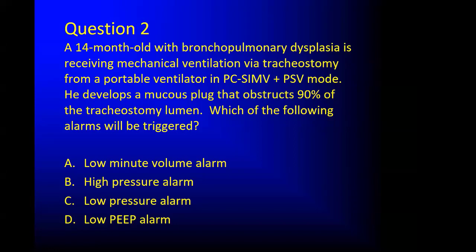Ooh, it's a horse race. All right, well, most people chose the high pressure alarm, but in fact that will not alarm when you are using a pressure control mode. All that will happen is you will hit your pressure. It won't deliver any breath to the baby, but you will not get a high pressure alarm when you're in pressure control mode with an obstruction. Instead, the alarm that will most likely go off would be your low minute volume alarm because you're not delivering the breath to the baby.